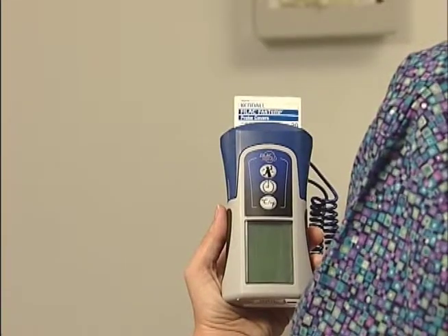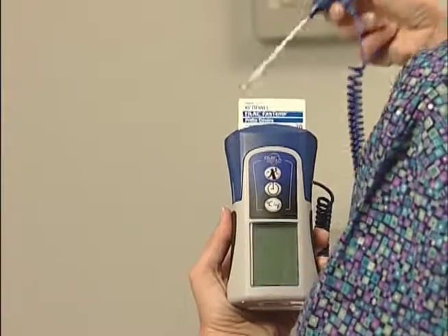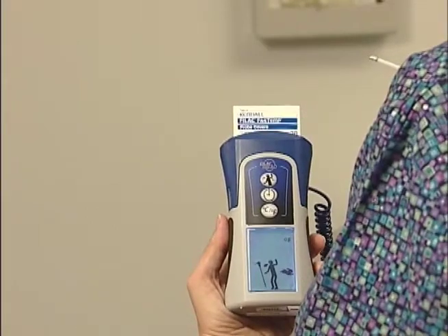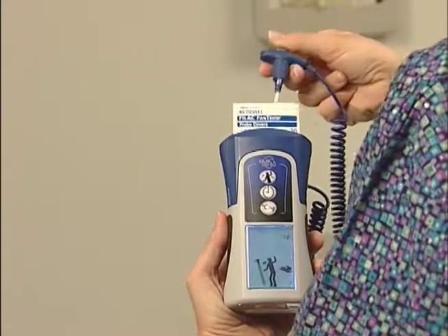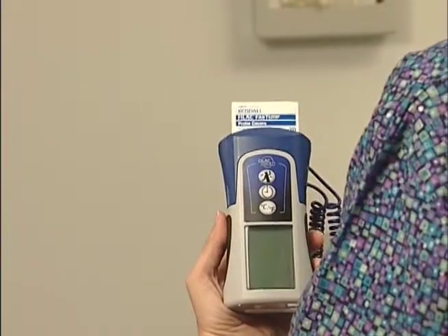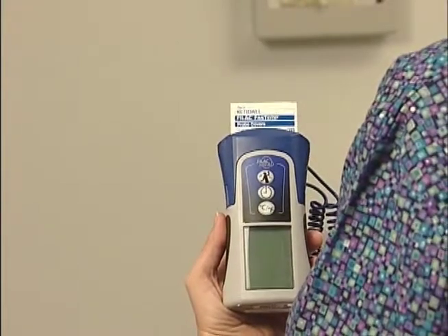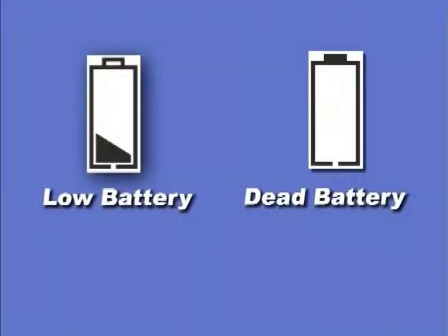Additional features of the Filac Advanced Thermometer include an auto-on when the probe is withdrawn from the probe well and auto-off when the probe is returned to the probe well. This helps to conserve battery life. There are also two battery indicator icons, one for low battery and one for dead battery. The battery should be replaced if either icon appears on the screen.